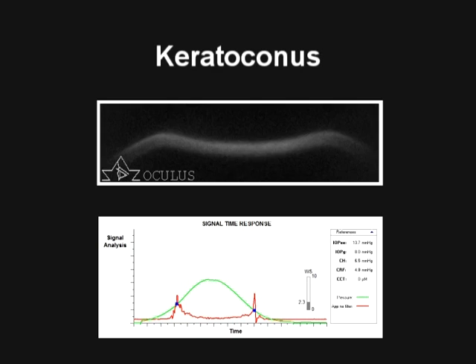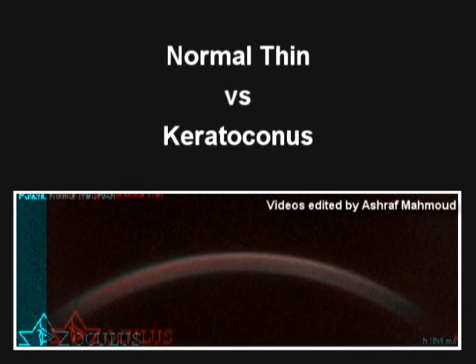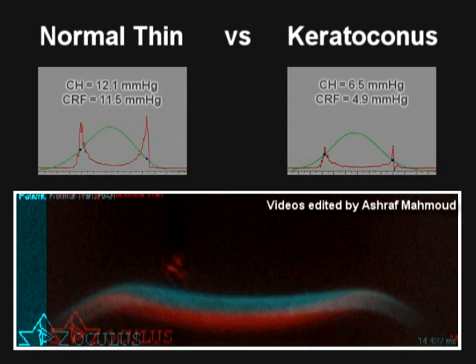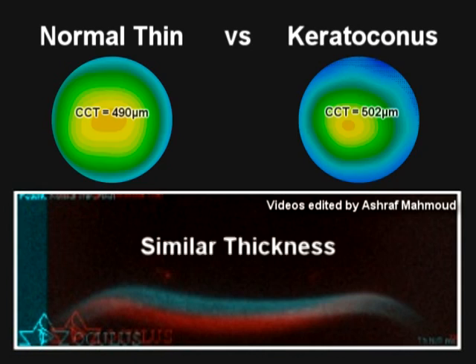Shown here is a cornea with keratoconus that has similar thickness to the previous normal cornea. If the two corneas are pseudo-colored and then superimposed and synchronized in time during the application of the air puff, one can appreciate the differences in the deformation characteristics. The red keratoconic cornea deforms almost a full corneal thickness more than the normal cornea with similar thickness and similar IOP.